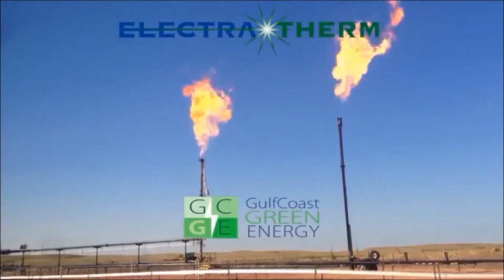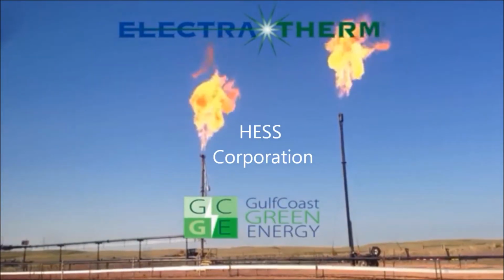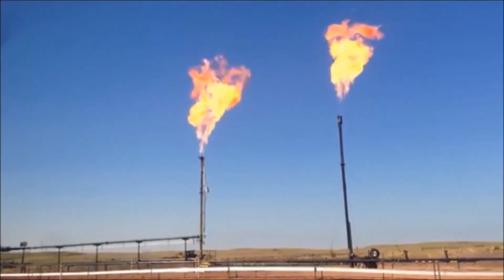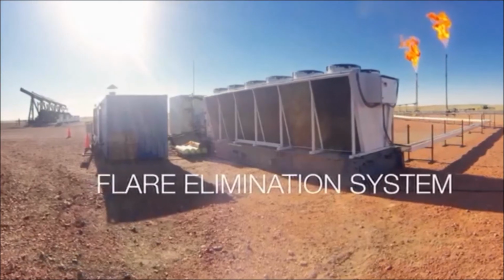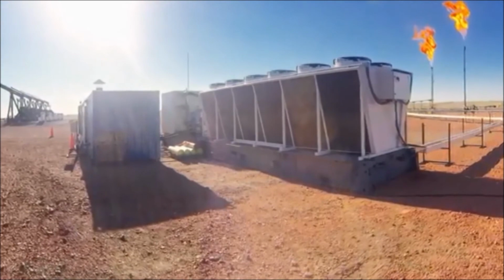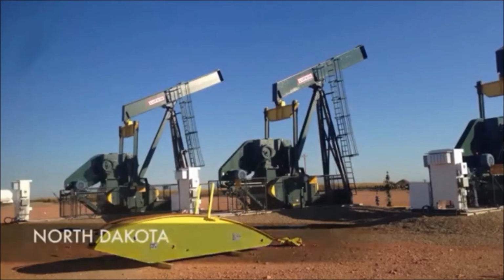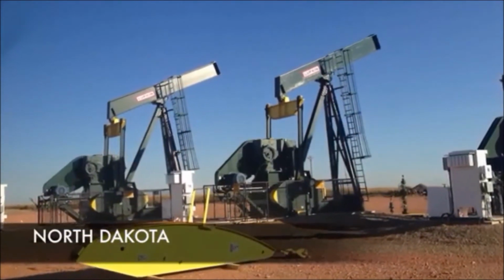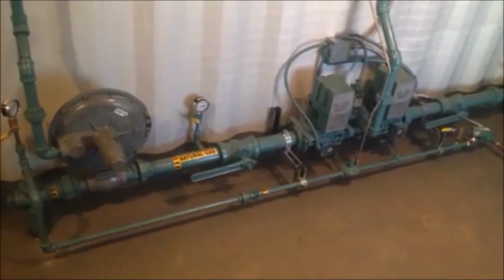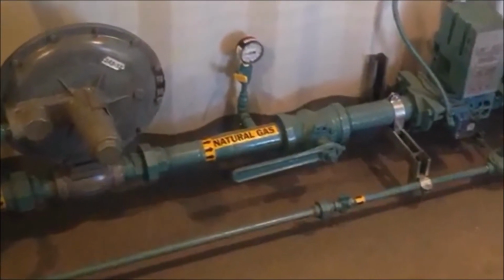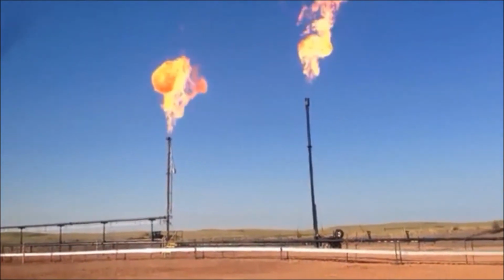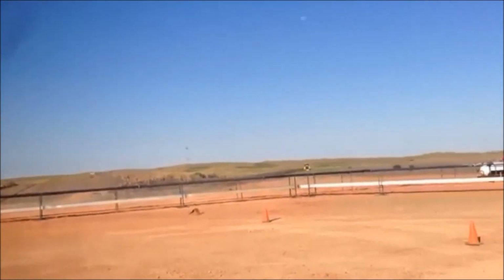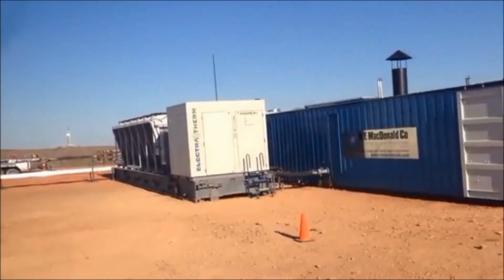ElectraTherm, Gulf Coast Green Energy, and a major oil and gas company commissioned the first flare elimination system using heat-to-power technology. Located at an oil well in North Dakota, ElectraTherm's Power Plus generator captures the natural gas that would otherwise be flared to generate low-emission electricity and reduce or eliminate on-site flaring.